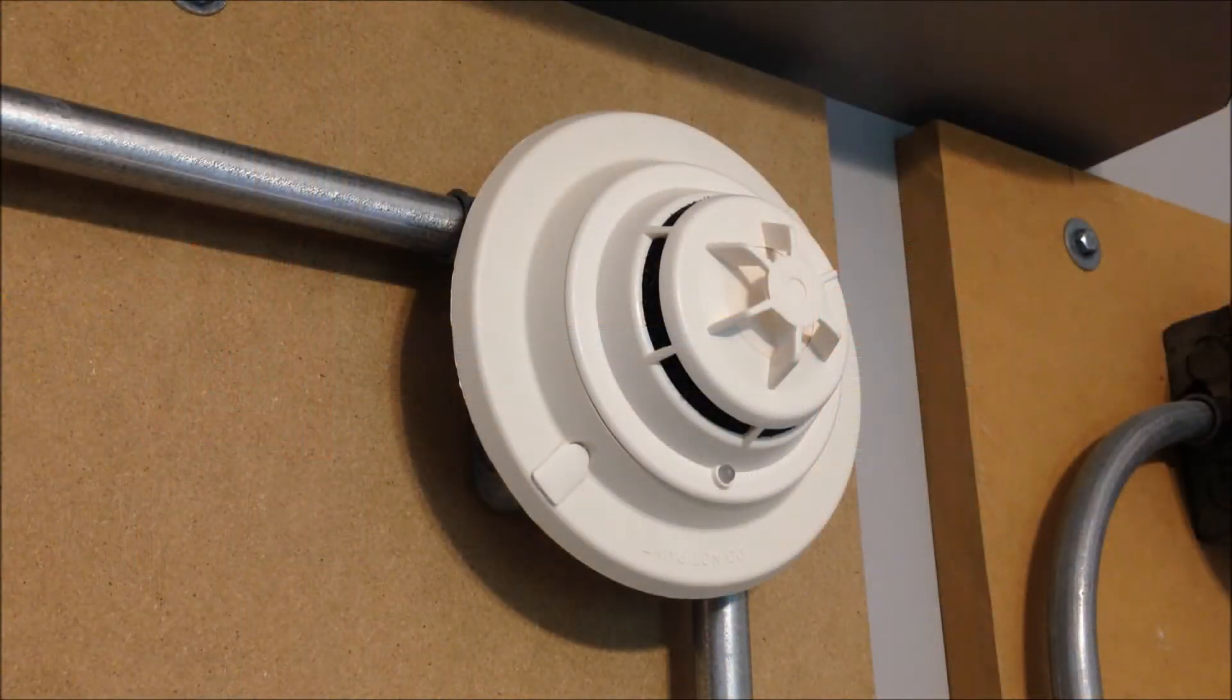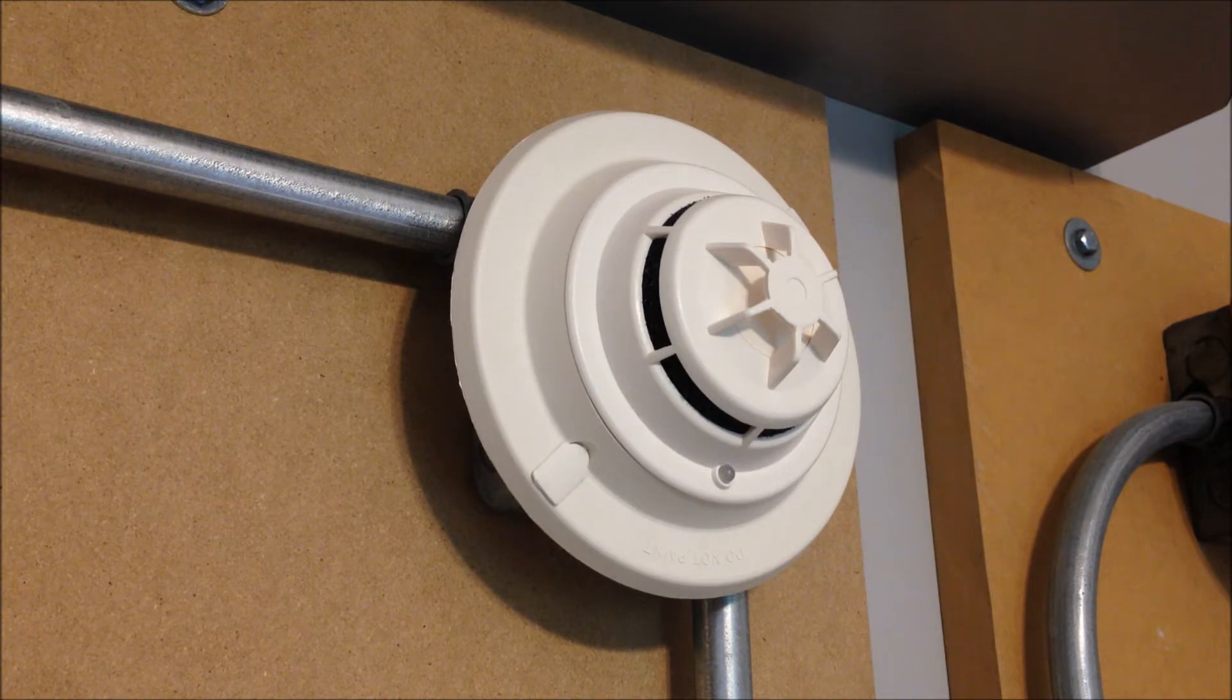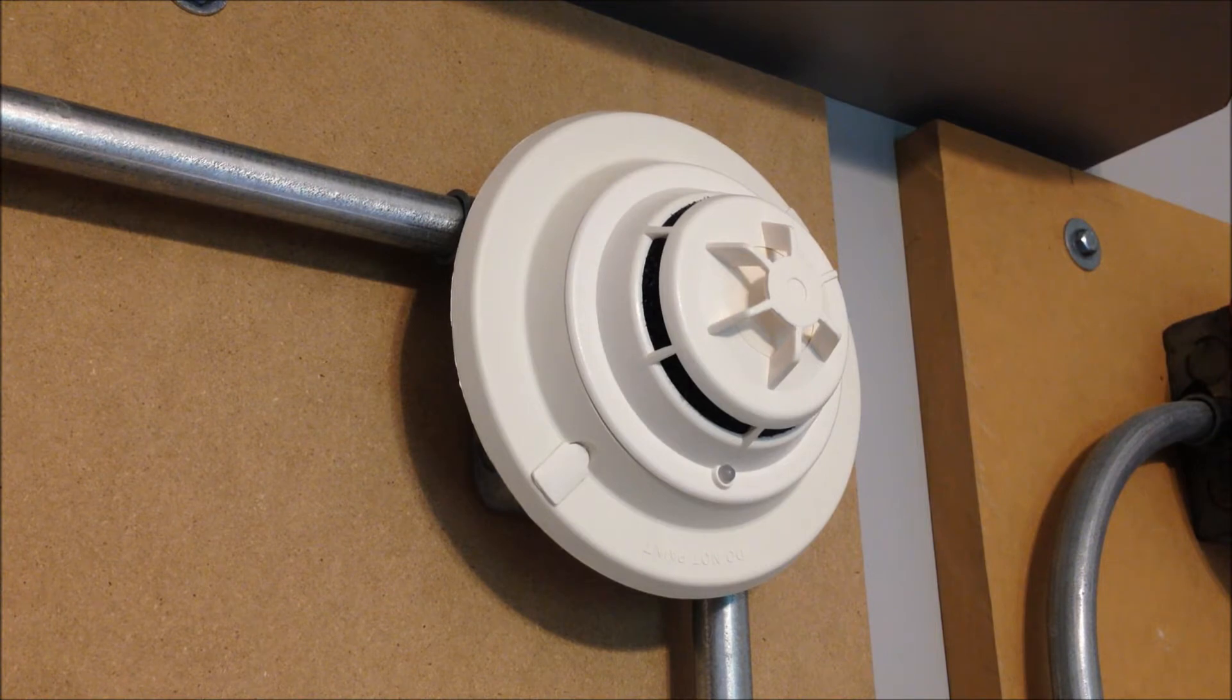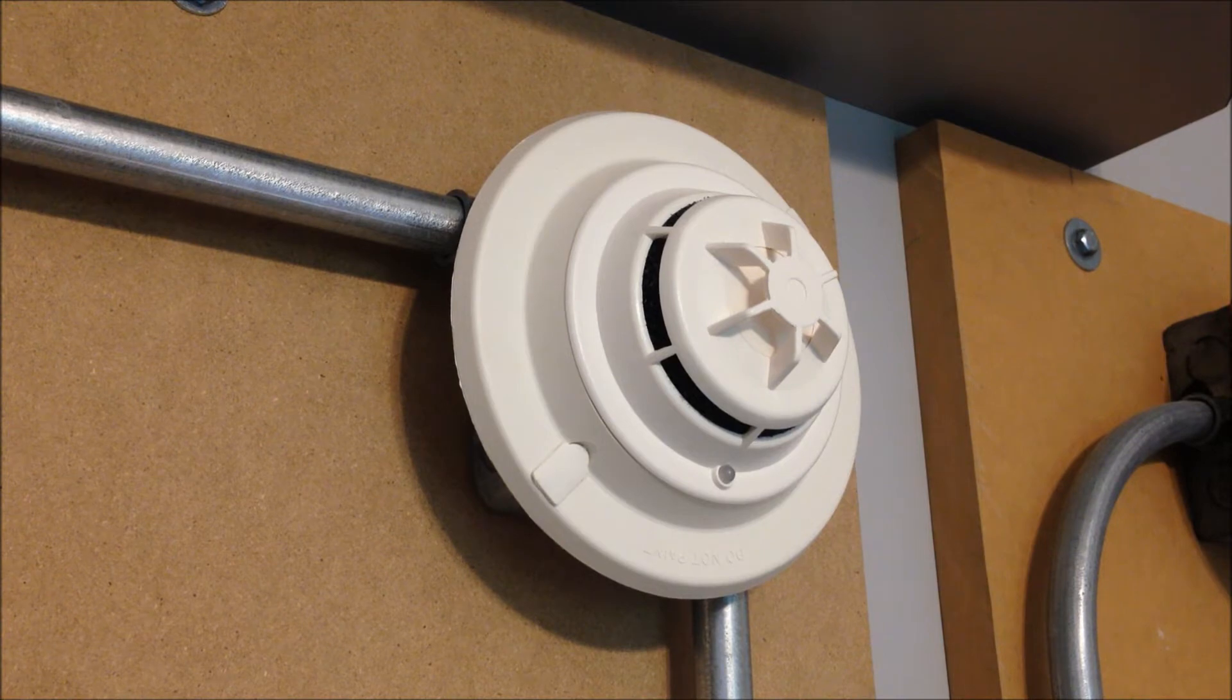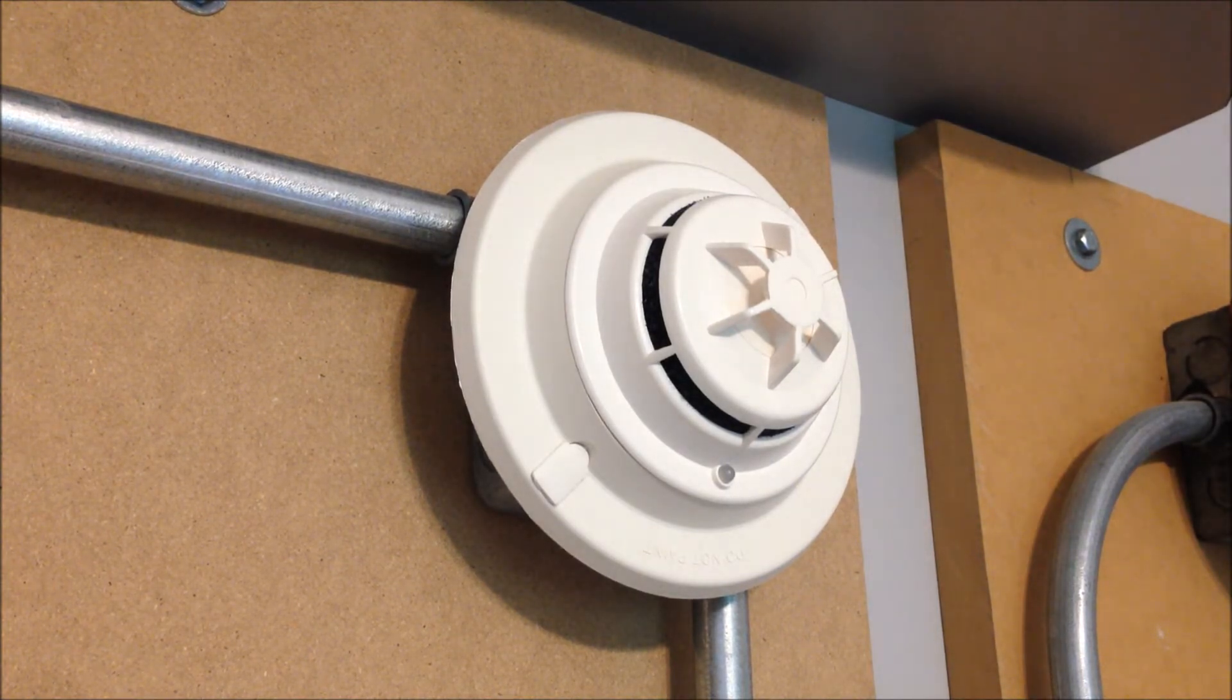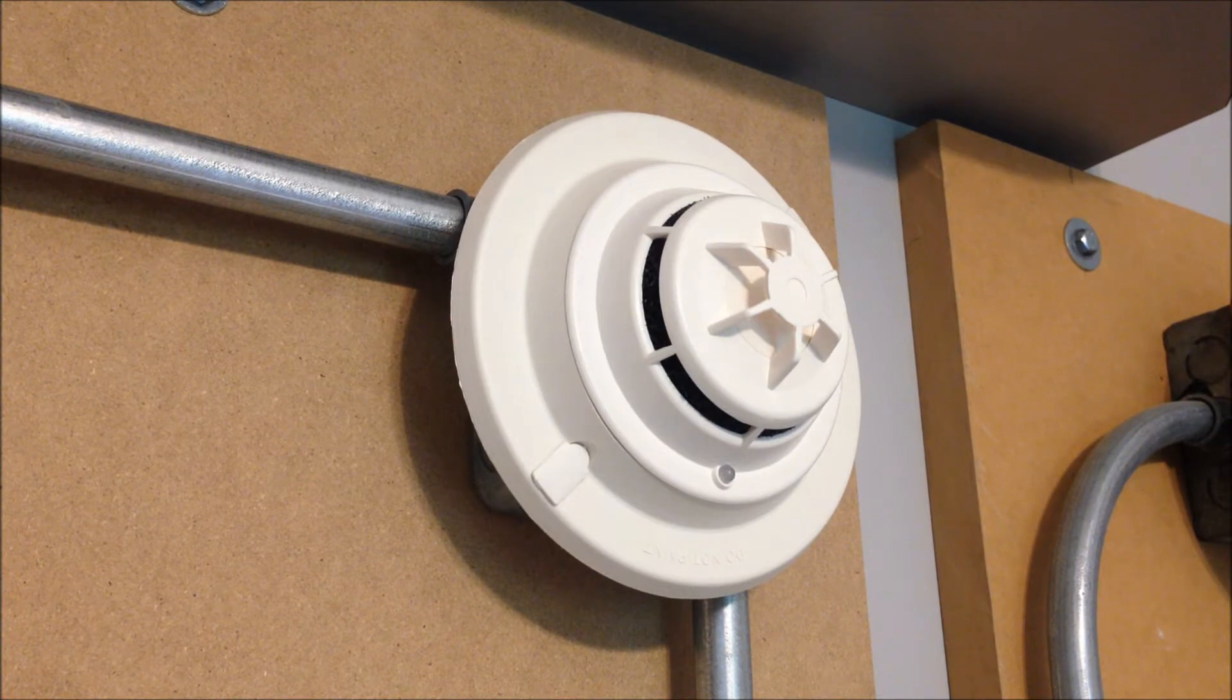Although the pull stations are nice and all, in this video, we're finally going to get an opportunity to test out the Siemens Cerberus Pyrotronics PE-11T smoke detector that's been mounted above the panel for a while and kind of hasn't made its way into the system test videos yet. This is a combination photoelectric and thermal heat detector. And it's a two-wire device. It's exclusive to the Siemens Cerberus Pyrotronics branded devices. And this is actually a really expensive smoke detector.